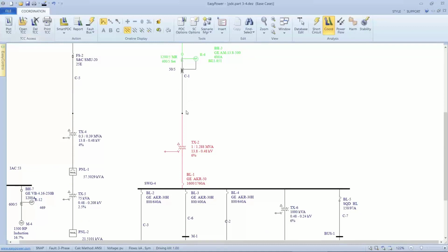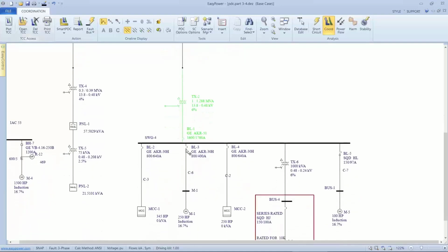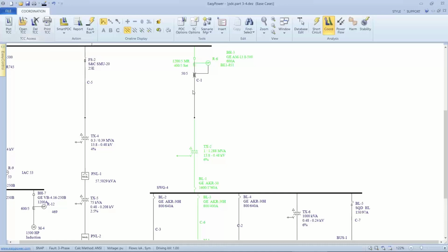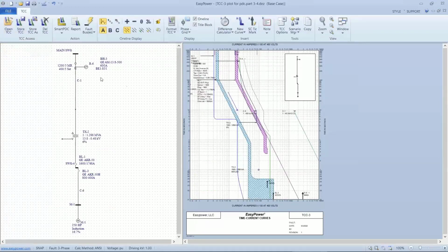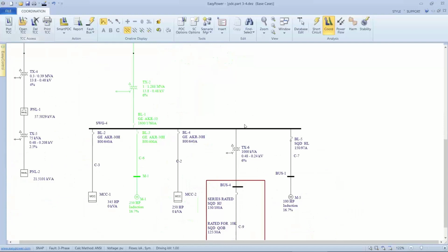So this is a question that has come up before, and that is, how do we know that it's going to coordinate with the other devices? So again, I'm going to start back with this original plot. Okay, and basically we've slowed down the upstream relay and the upstream main breaker. And we're going to put that same plot, overlay it with the smaller motor. So let's not save that. Let's go ahead and add this over here. And the question is, is this going to be coordinated?